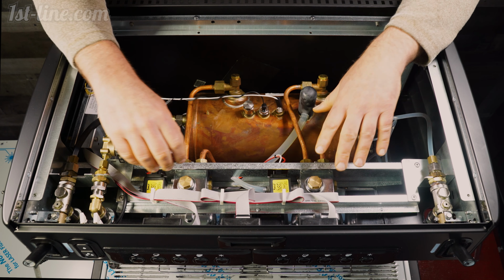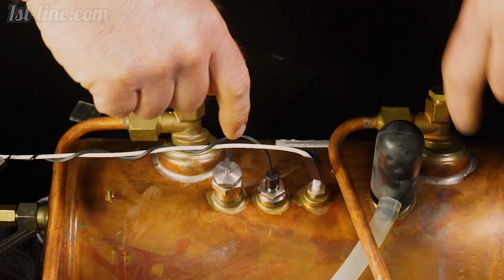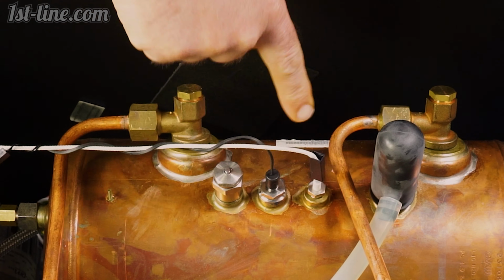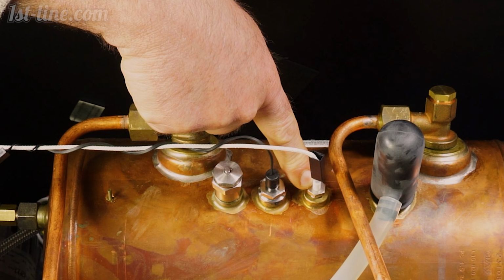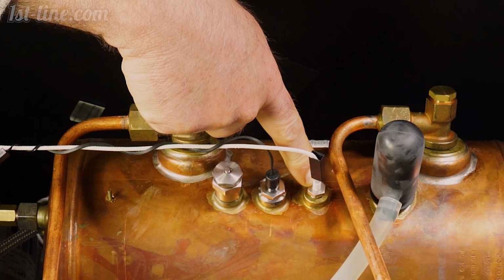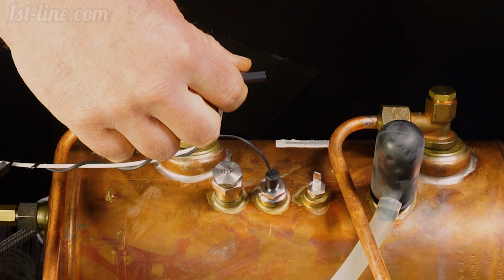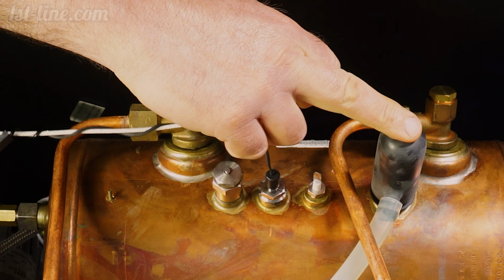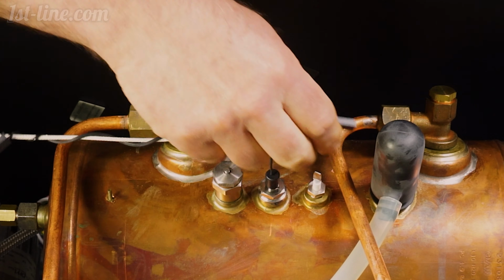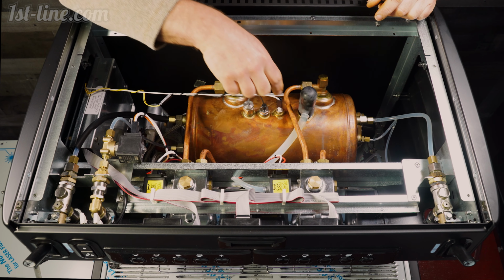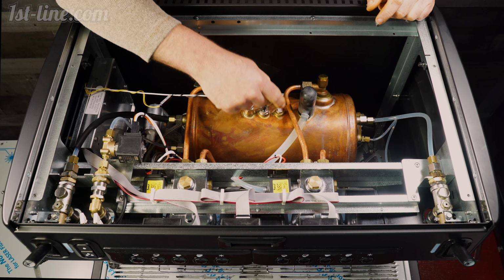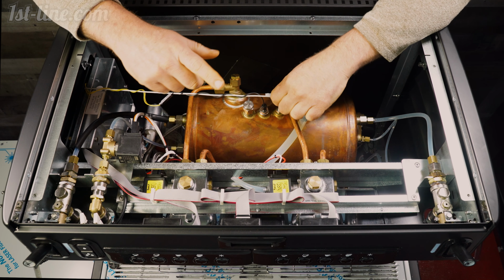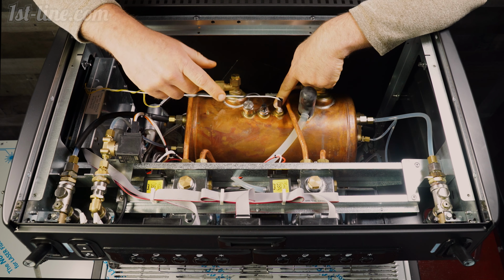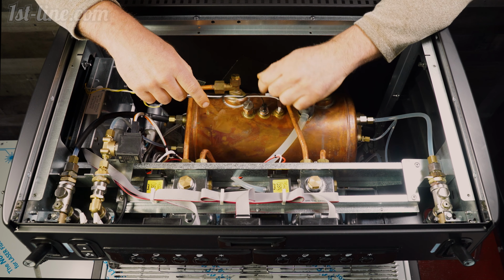That water stays different. Now the water in the boiler typically is monitored by this probe for the water level. And if you disconnect this, it'll keep filling the boiler more and more and more, and it'll come out of the safety valve, and this is the bleeder valve. So if you have an overfill situation, it's usually check this part right here. Usually you get some type of water corrosion or contamination, and that just needs to be cleaned.